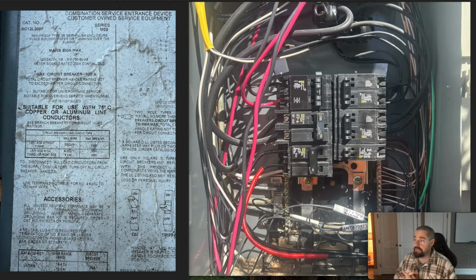They're just always hot. The only way to kill power to this panel is one, either to cut the tag on the meter and yank it out of the meter socket, breaking that connection between the utility and the service equipment, or two, having the utility come out and drop power at the transformer so that you can go in and work on this equipment.